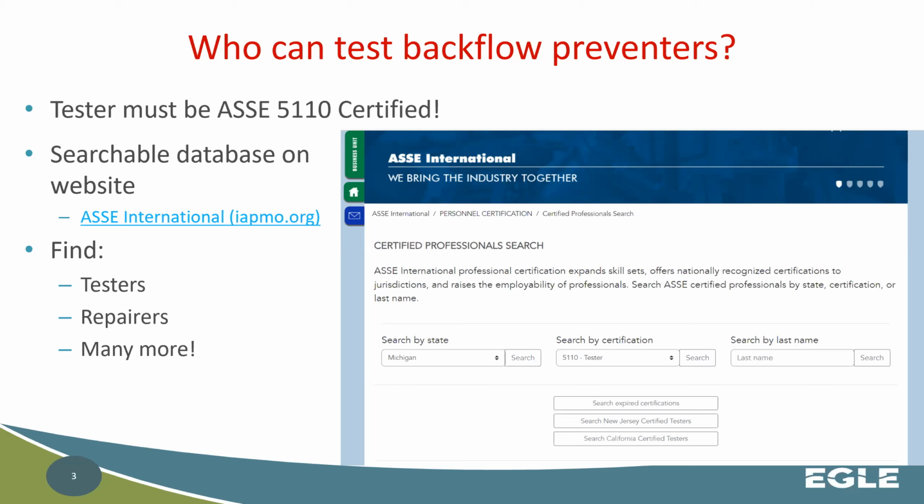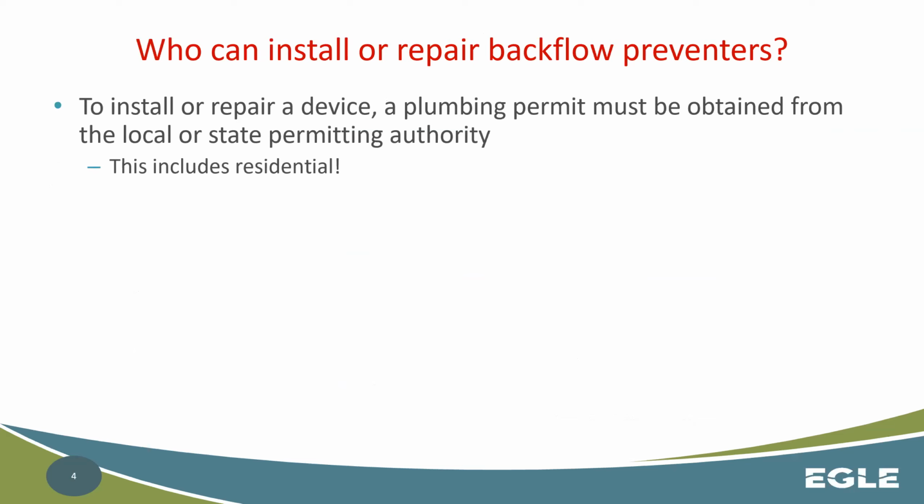Tester must be ASSE 5110 certified, must be. Okay. This is a state law. It says that now. So who can install them? Okay. So to install or repair a device, a plumbing permit must be obtained from the local or state permitting authority.